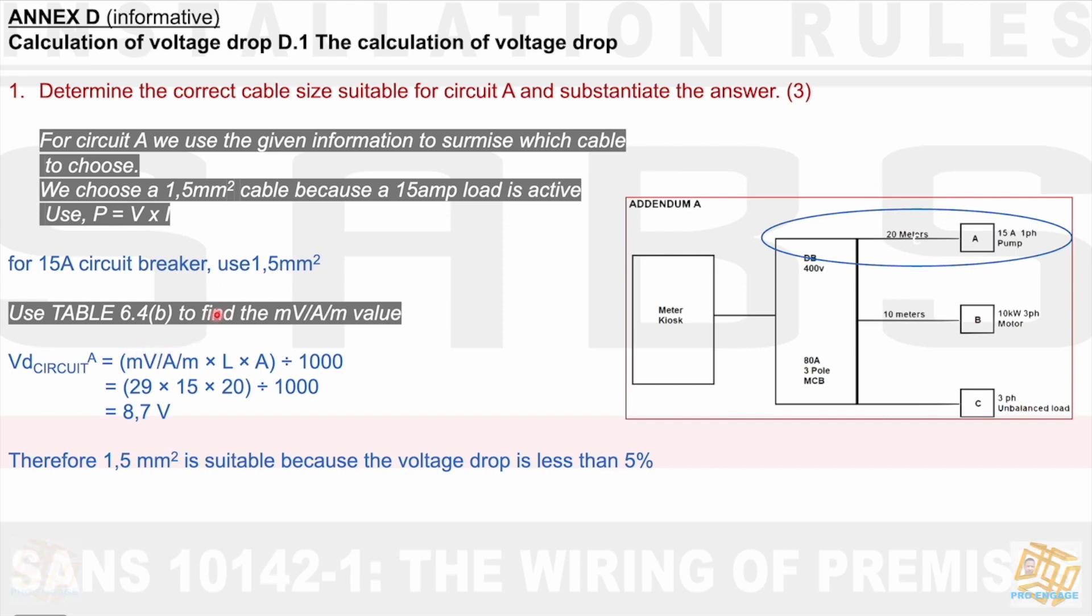We then say we go to that table and we find that value for mV/A/m. And that would be 29 for 1.5 mm², checking on your tables, times a distance of, sorry, this is amps, and a distance of 20 meters. I'll swap those two. And then divide that by 1000, I get 8.7 volts. Therefore, 1.5 mm² cable is suitable because the voltage drop is less than 5%.